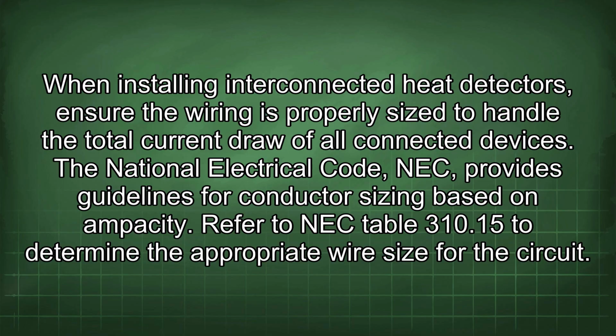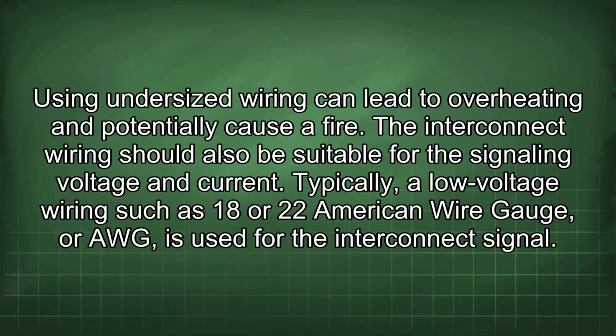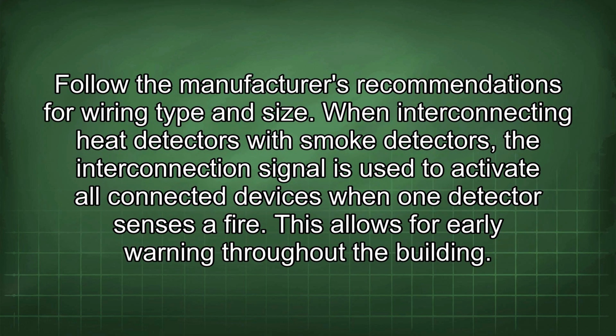When installing interconnected heat detectors, ensure the wiring is properly sized to handle the total current draw of all connected devices. The National Electrical Code (NEC) provides guidelines for conductor sizing based on ampacity. Refer to NEC Table 310.15 to determine the appropriate wire size for the circuit. Using undersized wiring can lead to overheating and potentially cause a fire. The interconnect wiring should also be suitable for the signaling voltage and current. Typically, low voltage wiring such as 18 or 22 American Wire Gauge, or AWG, is used for the interconnect signal. Follow the manufacturer's recommendations for wiring type and size.